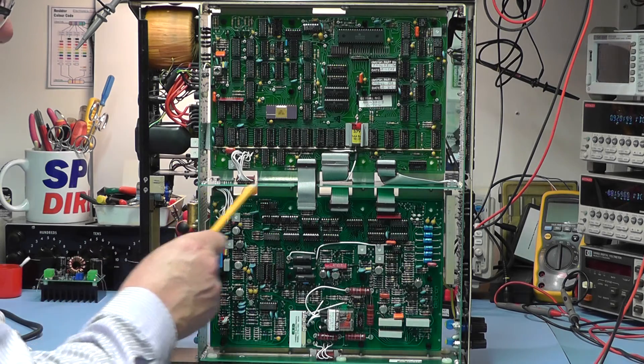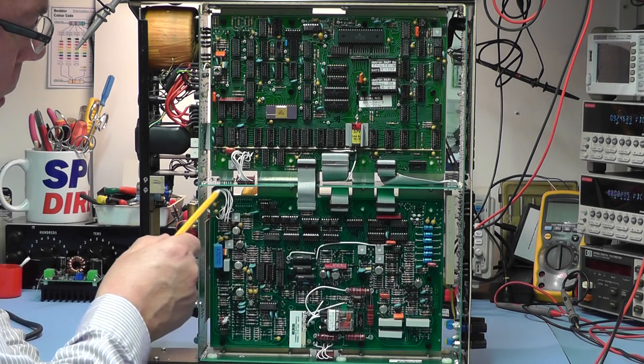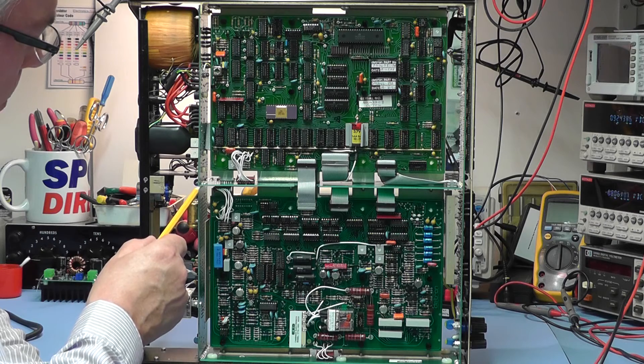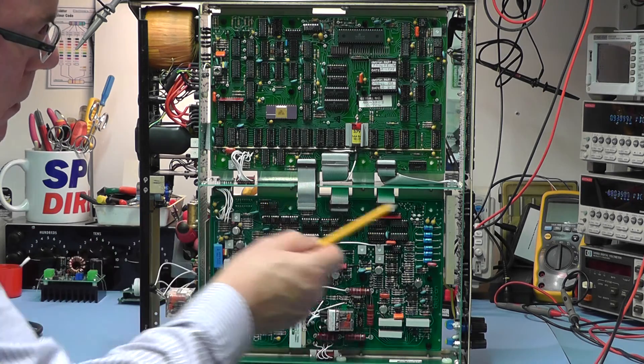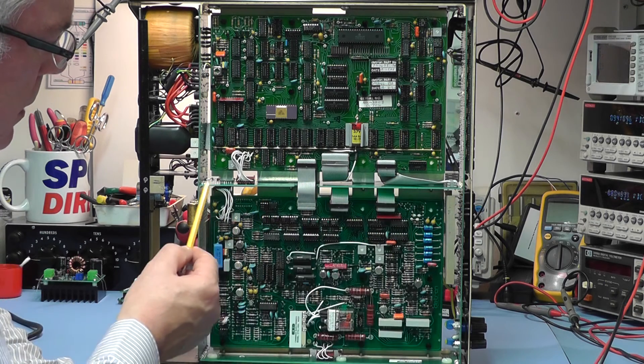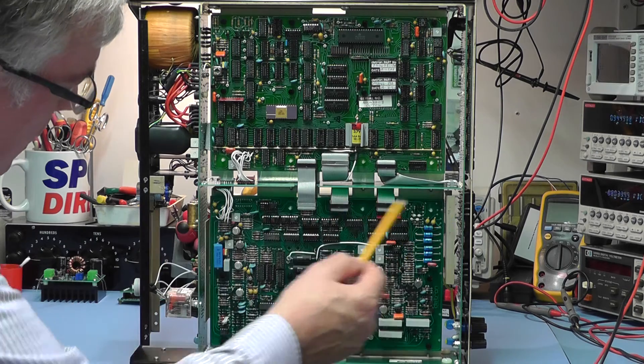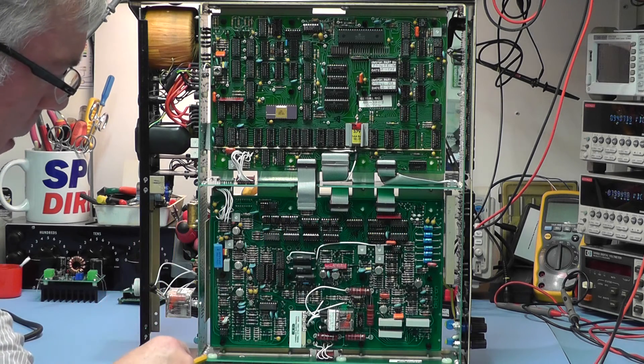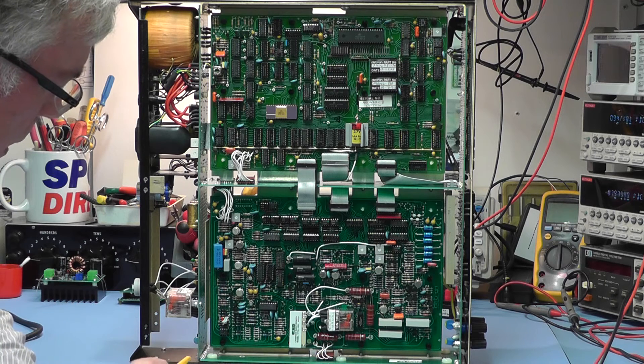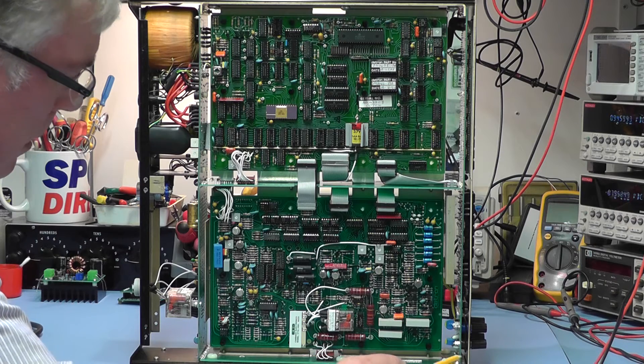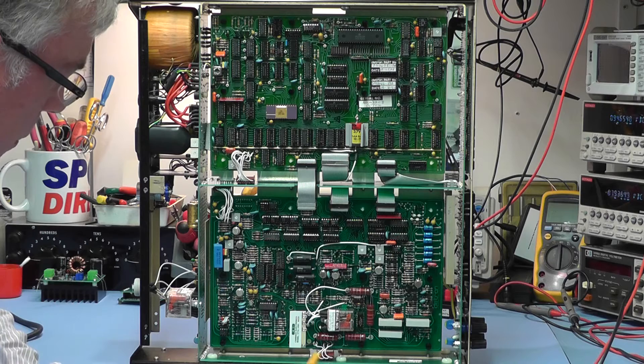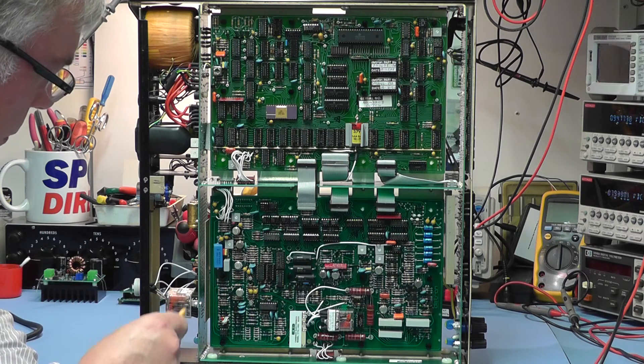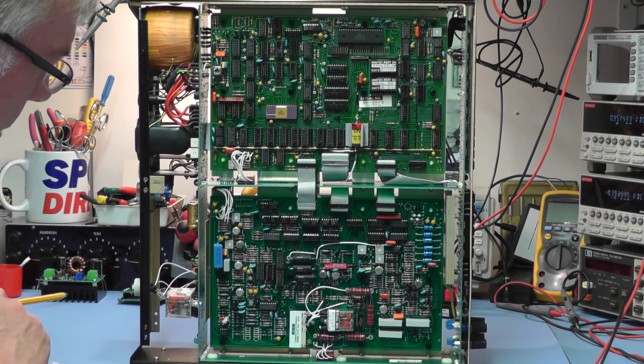You'll notice here in the middle of the unit we have a module printed circuit board going from the rear panel here to the front panel. That's providing the internal connections from rear to front. They do it with the means of a printed circuit board. And similarly on the bottom here we have another one running from the back panel here and the front panel and that's providing the input signals going to the circuitry here to be able to switch them over to the rear connectors on the back.